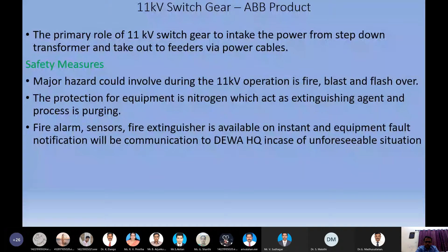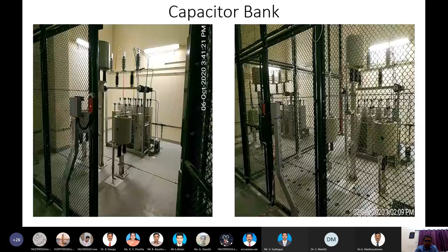This is a capacitor bank room. The capacitor bank is not easily accessible. It has a cage, grille access, and it also has a nitrogen suppression system, and a specific kind of fire extinguishers. Here we recommend CO2, carbon dioxide fire extinguishers, 5 kgs, which will be placed at the exit. We have 3 capacitor banks, since we have 3 IDTs, since we have 3 ETs.